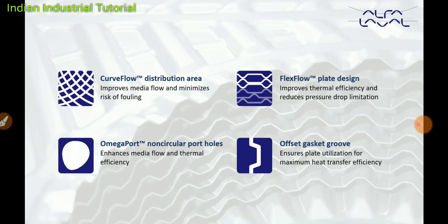Great. So there's one last question by Mehul Rathod. How to improve efficiency of heat exchanger in working conditions? Yeah, in working condition, timely cleaning of the heat exchanger is very much essential, because when the heat exchanger is designed, the thickness of the plate is 0.5 millimeter, but over a period, because of scaling, the heat exchanger plate thickness goes up to 1 millimeter also, and at that time heat transfer efficiency goes down.